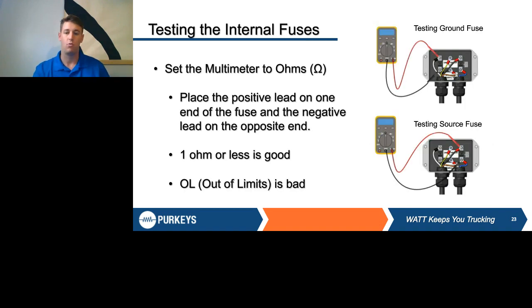When you see this, there are a couple ways to test those fuses. One is to get your multimeter, set it to ohms, and measure the resistance across the fuse. Place the positive lead on one side, negative lead on the other - it doesn't matter which side - just make sure they're across that fuse. You want a reading of 1 ohm or less; that tells you the fuse is good. If it reads OL, that means it's out of limits, or bad.